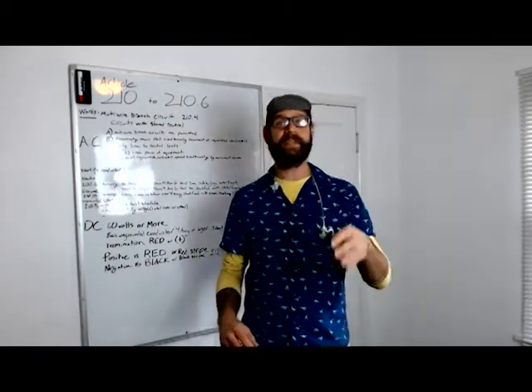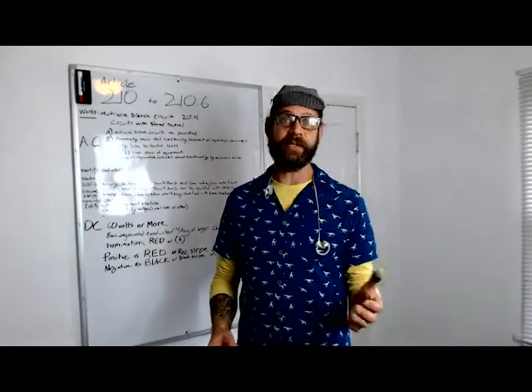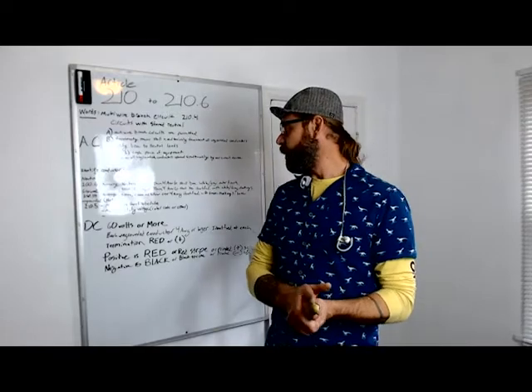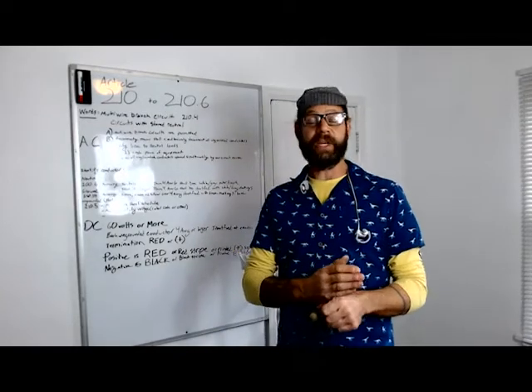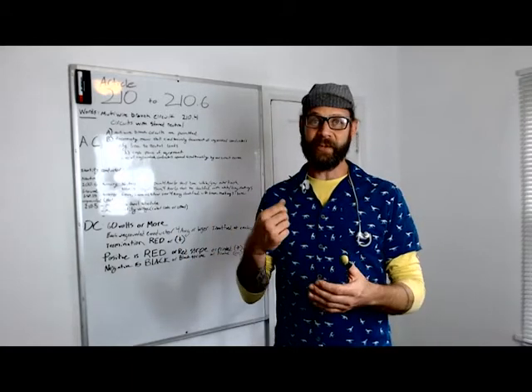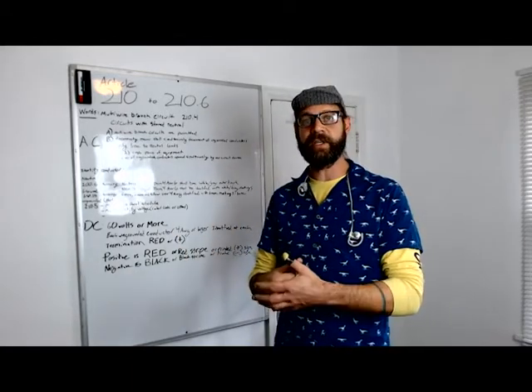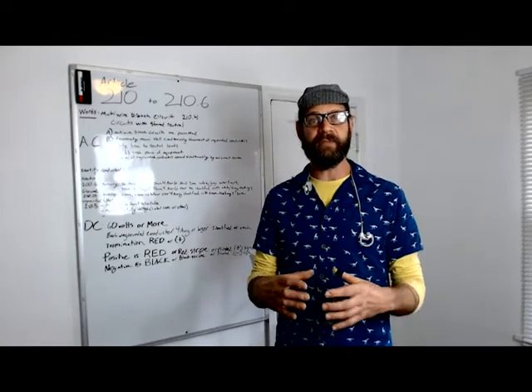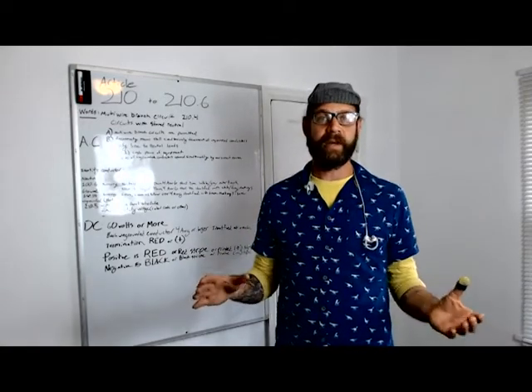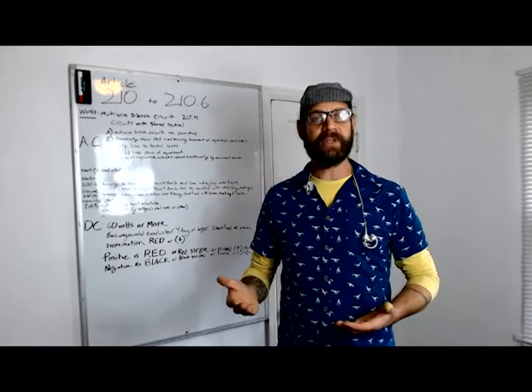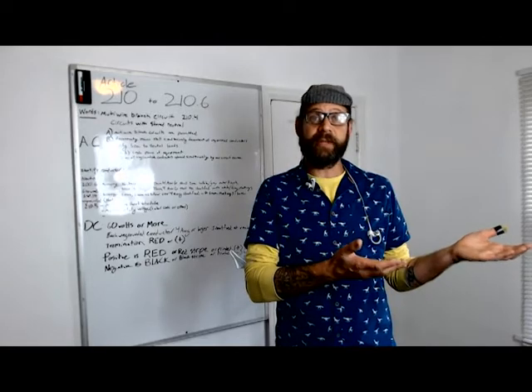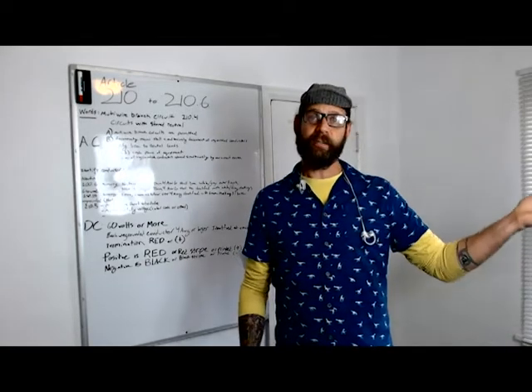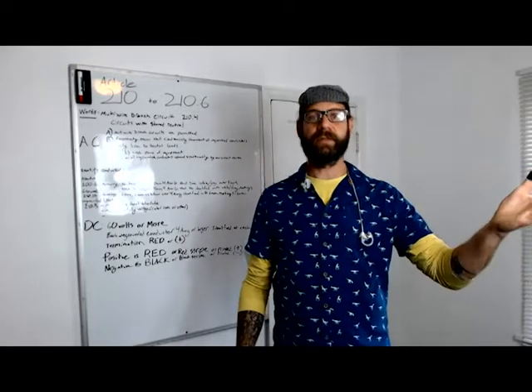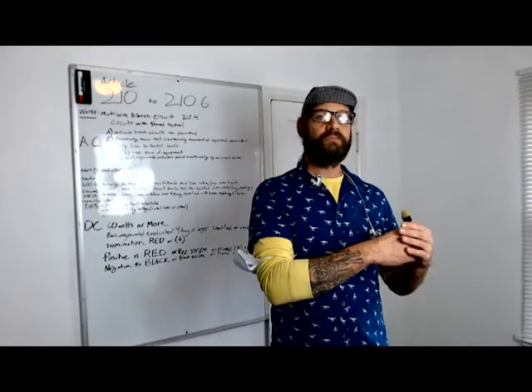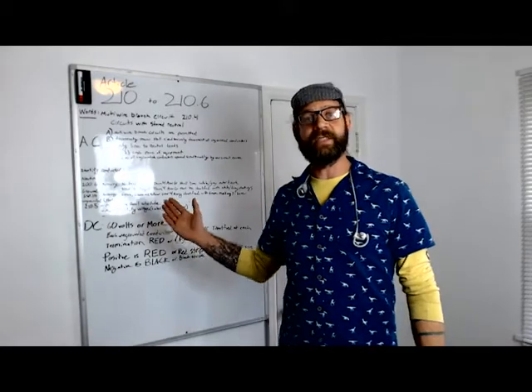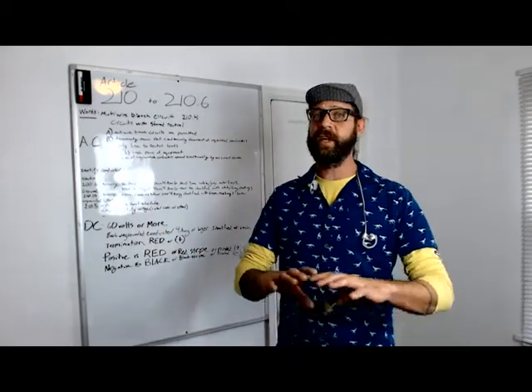It's not required that you use that exact color code, although it is industry practice, and if you use a different color code, it's going to be real jammed up. So try and use that color code, but you must identify for the voltage. And the best way to do this is to color code in the standard way and to identify and label every box. Then you're going to be covered. The inspector's not going to jam you up, because he's going to know what the color code means. The color code is going to be listed on the panel schedule. It's going to say brown, orange, yellow. Brown is going to be A phase, orange is going to be B phase, yellow is going to be C phase. No problems. Just having that color means that's the voltage it is. Also, it's written on the box what voltage it is. Inspectors aren't going to have a problem with that.